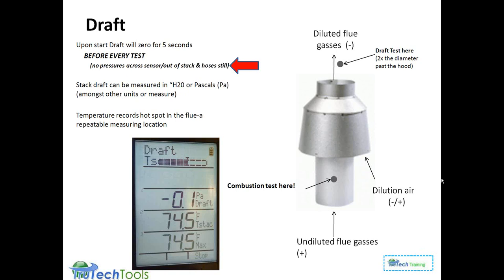Question came up for differential pressure. Why does one need a different probe? You don't actually need a different probe. You can just slip a hose over the minus pressure port and then a tube or a hose over the flue gas probe end, making sure you fully cover the end of the probe tip. And you just need the hose in order to access the pressure zone. If that isn't clear, I could talk with you offline about this issue. We might cover it in another slide. But please remind me in the end if this isn't a clear answer for you.